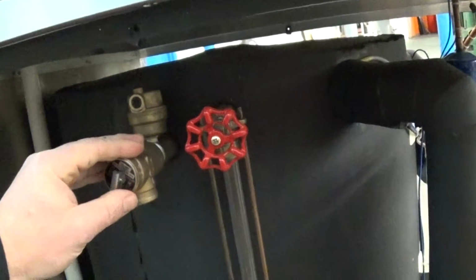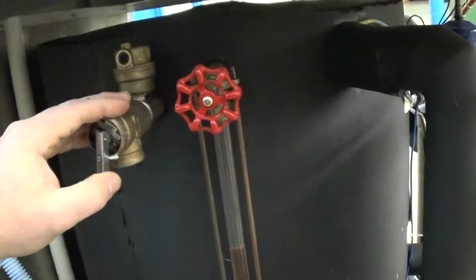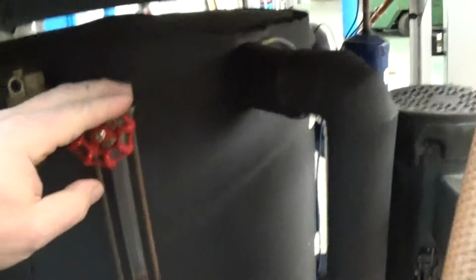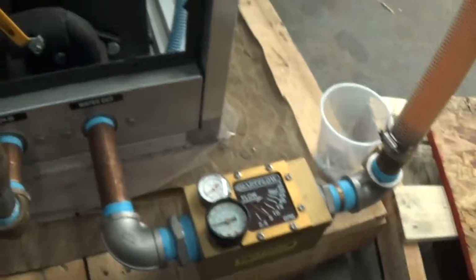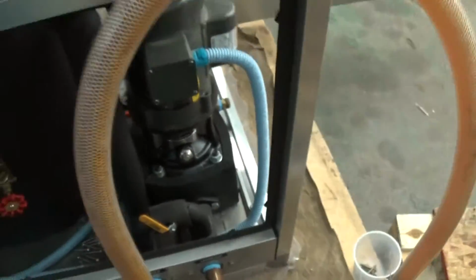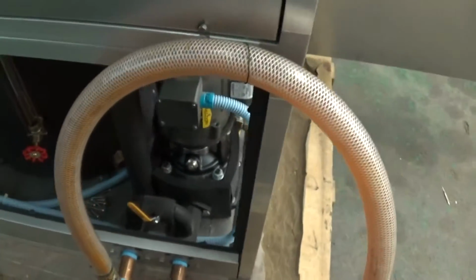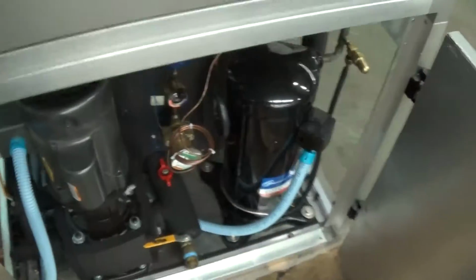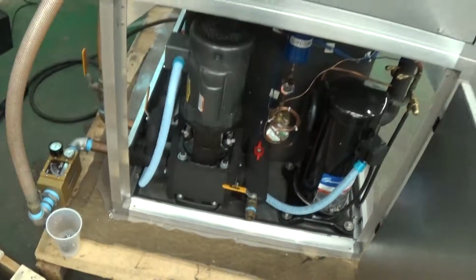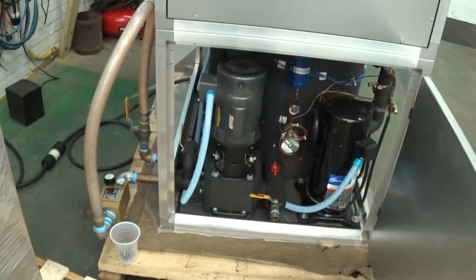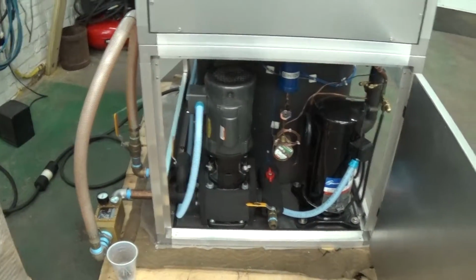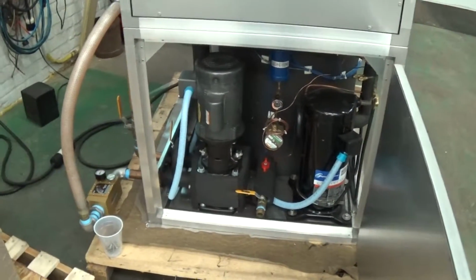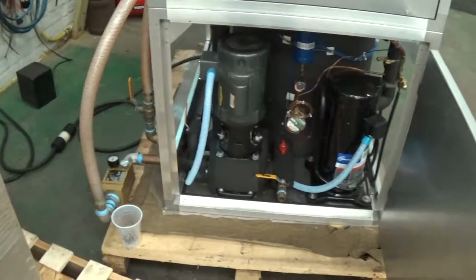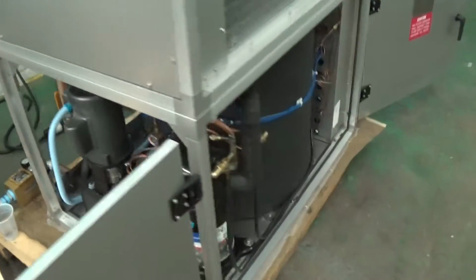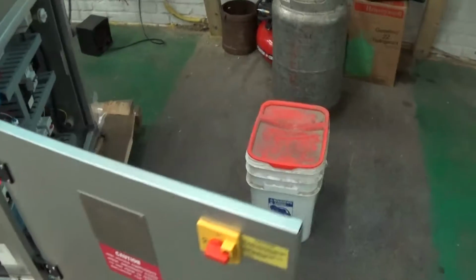We have a pressure relief valve here, just for excess pressure in the tank if needed. And then you also have your glycol reservoir. We got about half full right now for this testing. So this unit with the heat exchanger submerged in the tank, again, we're drawing out of the tank, out to your process, and then discharging back. We can discharge back at very, very low pressure into the tank because we're not pumping through like a braze plate heat exchanger or anything like that requires a significant pressure drop.